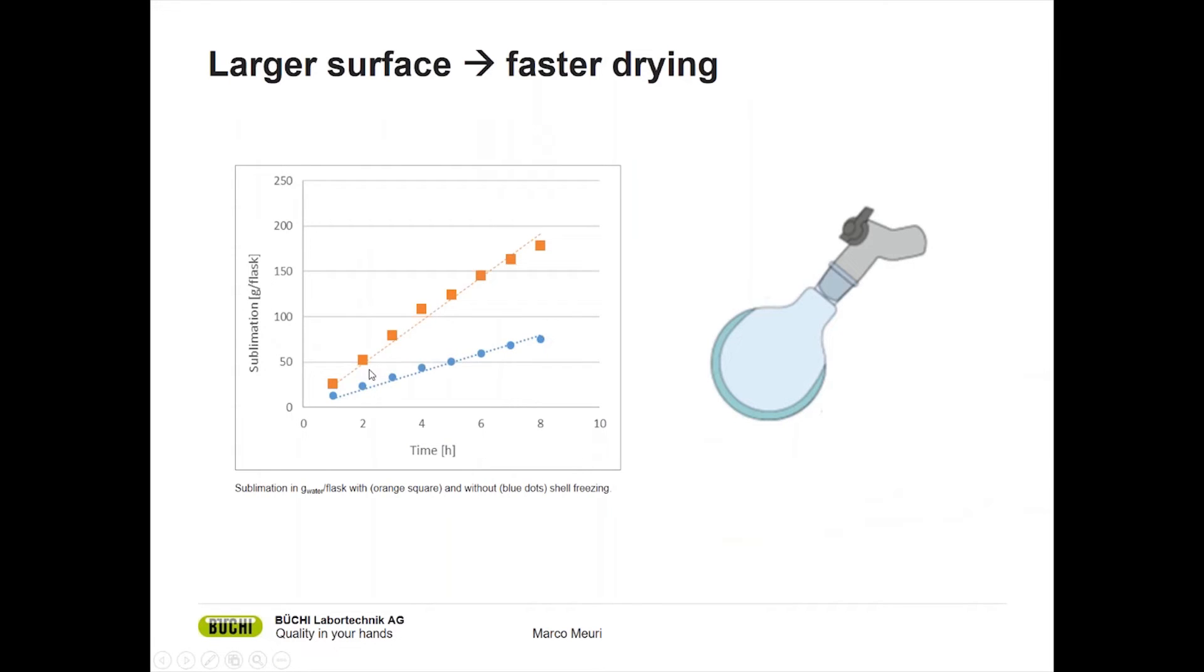What is the benefit if you freeze your sample in this way? If you look at the picture on the right hand side, this is a flask that has been frozen by shell freezing. What you can see is that the inner wall of the flask is covered with ice. Due to that, the surface of the ice is as big as possible. For freeze drying, or for the speed of freeze drying, it is very important that the sample has a big surface, because the bigger the surface, the bigger the area where the sample can actually sublimate. This will have a huge impact on the freeze drying of your sample.